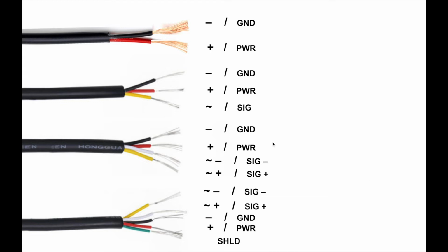Often, sensors that use 4 wires will have an optional 5th wire for shielding. This helps decrease the amount of noise picked up by the signal wires from the surrounding atmosphere, since sometimes these wires pick up electromagnetic waves in the air that can affect the signal voltage and thus the reading we get.